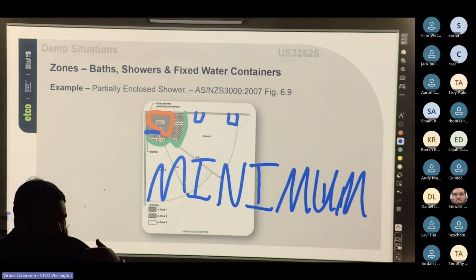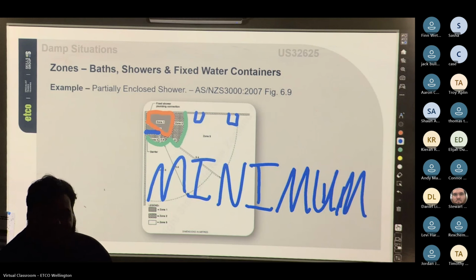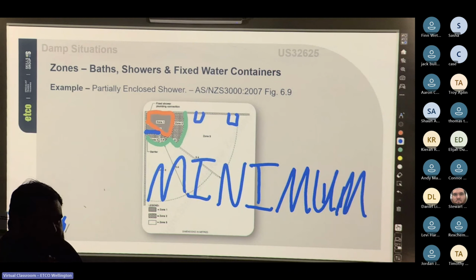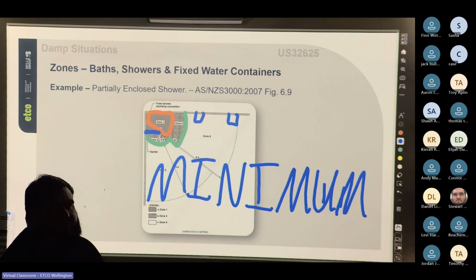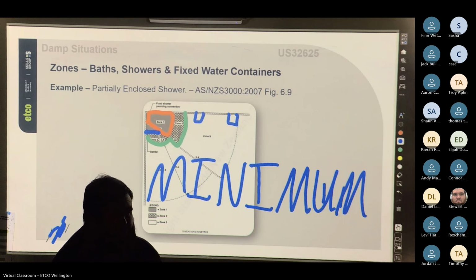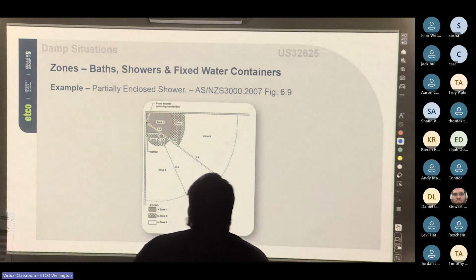I don't have long enough here to think about that kind of thing. But you're 100% right, for a hair straightener, for a hair dryer. But again, we can stick the socket outlet inside the medicine cabinet so that when you're using the shower, there's a barrier between you and the socket outlet. Or at least you have to open a cupboard before you get to the socket outlet. But that's just the way I would do it if I was doing a bathroom.